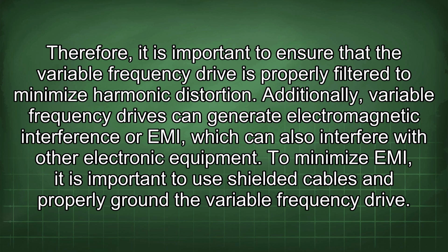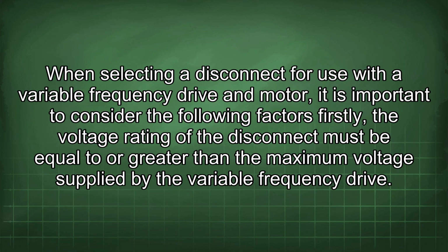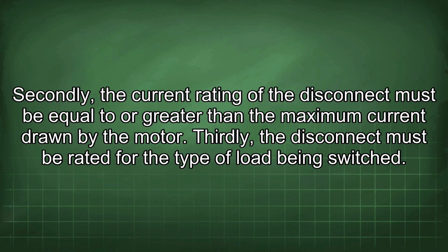Additionally, variable frequency drives can generate electromagnetic interference, or EMI, which can also interfere with other electronic equipment. To minimize EMI, it is important to use shielded cables and properly ground the variable frequency drive. When selecting a disconnect for use with a variable frequency drive and motor, it is important to consider the following factors. Firstly, the voltage rating of the disconnect must be equal to or greater than the maximum voltage supplied by the variable frequency drive. Secondly, the current rating of the disconnect must be equal to or greater than the maximum current drawn by the motor.